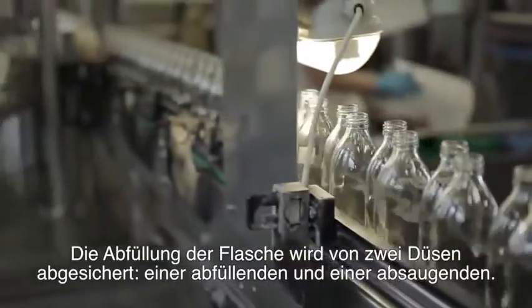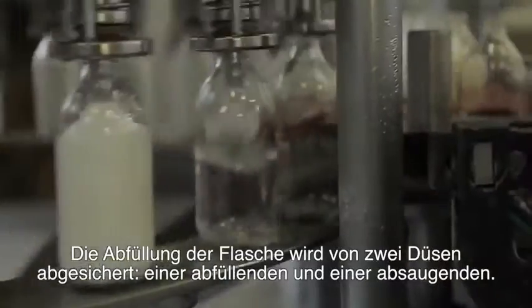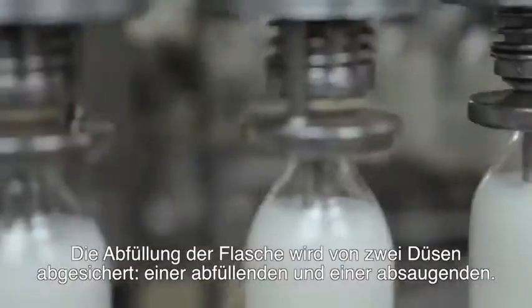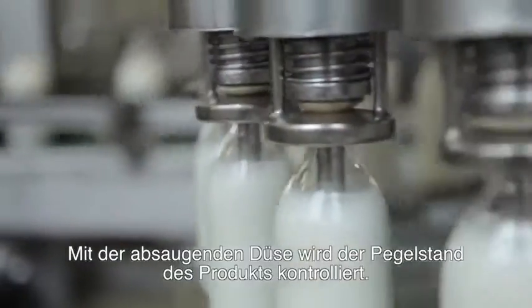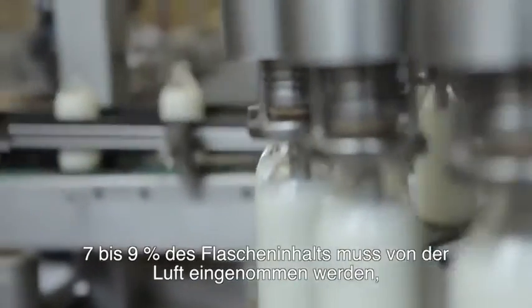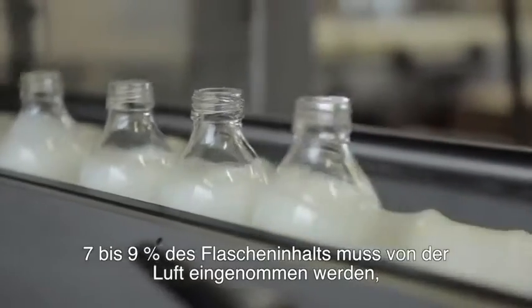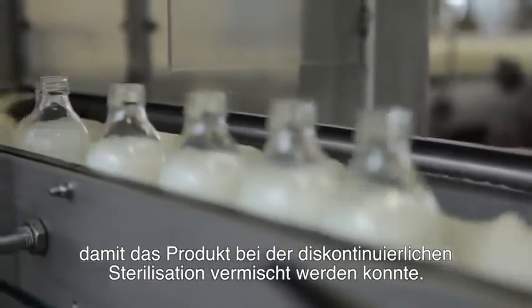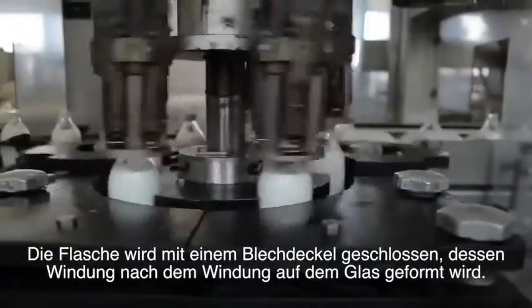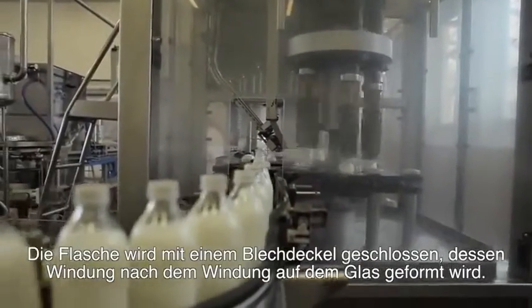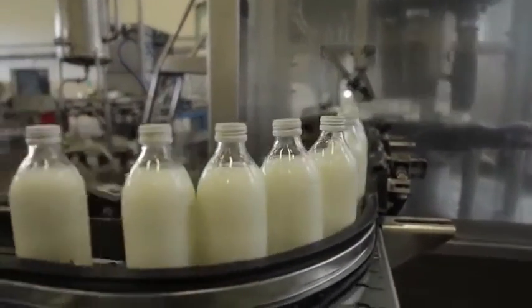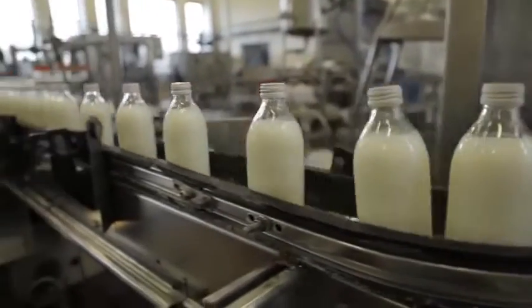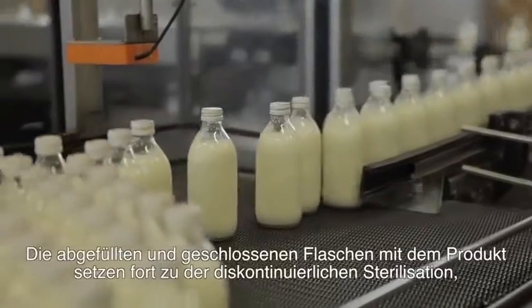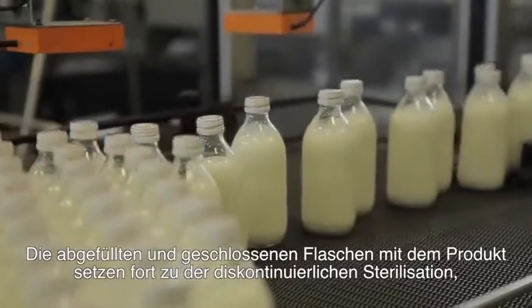Two nozzles provide the bottle filling. One fills and the other provides suction, controlling the product level. 7 to 9% of the bottle volume must consist of air so that the product can be mixed during the sterilization process. The bottle is closed with a metal cap, whose thread is formed according to the thread of the glass. The sealed bottles then continue on to the sterilization process.